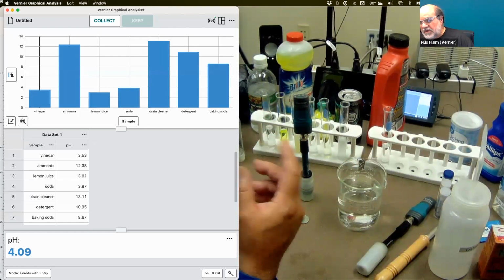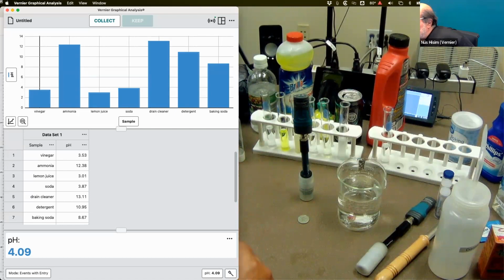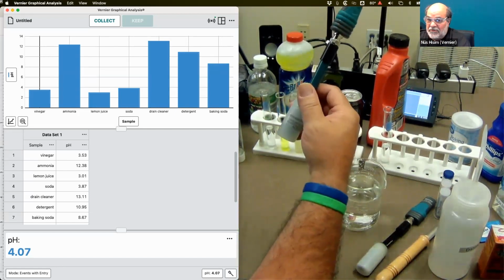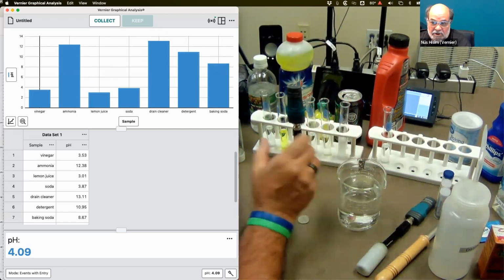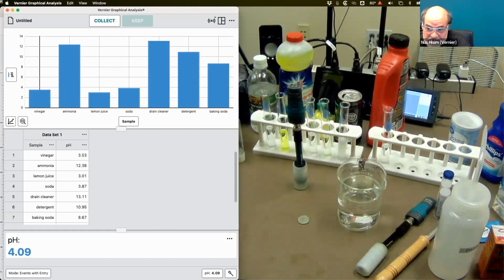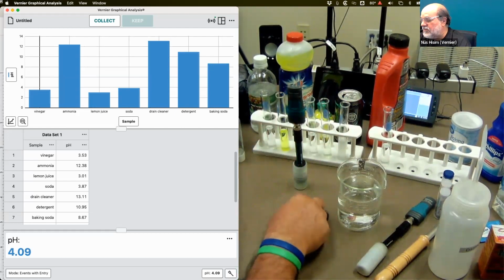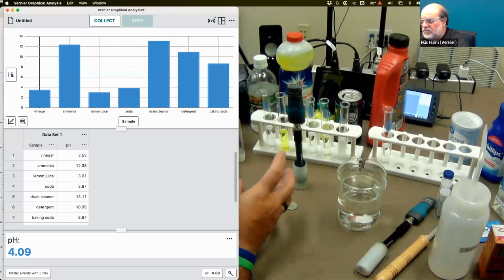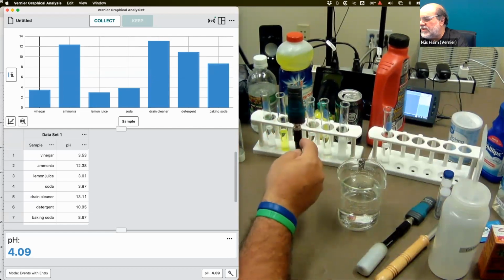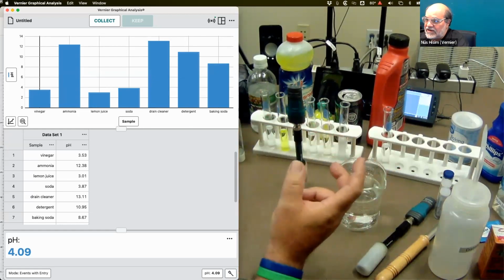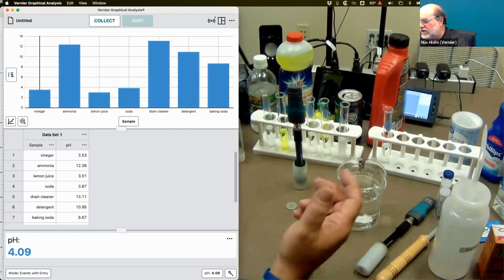But for most experiments, believe it or not, even for normal titrations, even if the pH was off by maybe half a unit or something, the equivalence point would be the same. It would just be higher or lower, but it would still be the same. So for a regular titration, as long as the storage solution's reading around 4, you could probably get by without recalibrating. Can you recalibrate the sensors? Of course. The beauty of the GoDirects now: the voltage output of the system and how that relates to pH is not linear. So we were faking it a little bit with our 2-point calibrations.